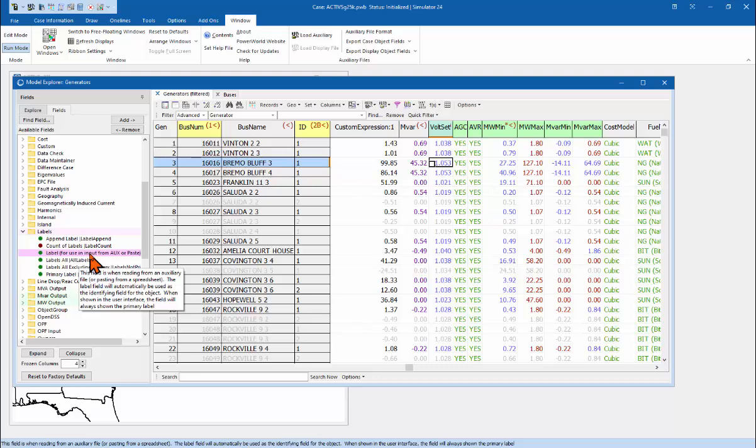And normally when you're opening a new case from an industry source like a raw file or an EPC file, that would not be populated. It would, however, probably be populated in most CSV files that we can read in from EMS systems. So that's kind of a nice feature of those, is that they generally don't rely on bus numbers to be a key field, which is good because they're normally full topology models and the bus numbers are not consistent from one system topology to the next.